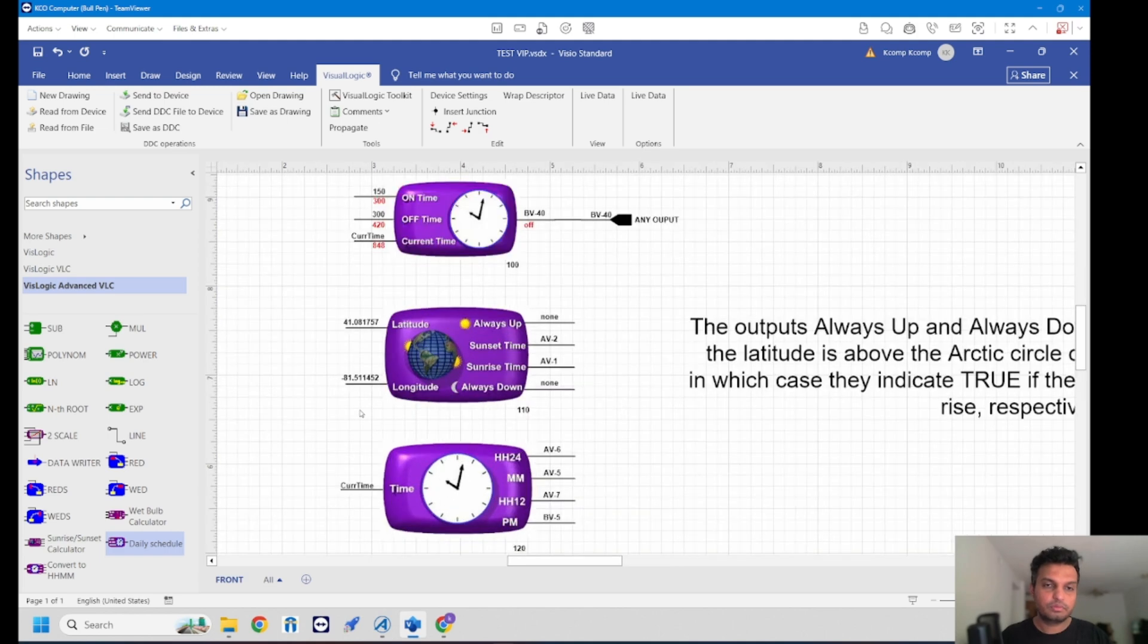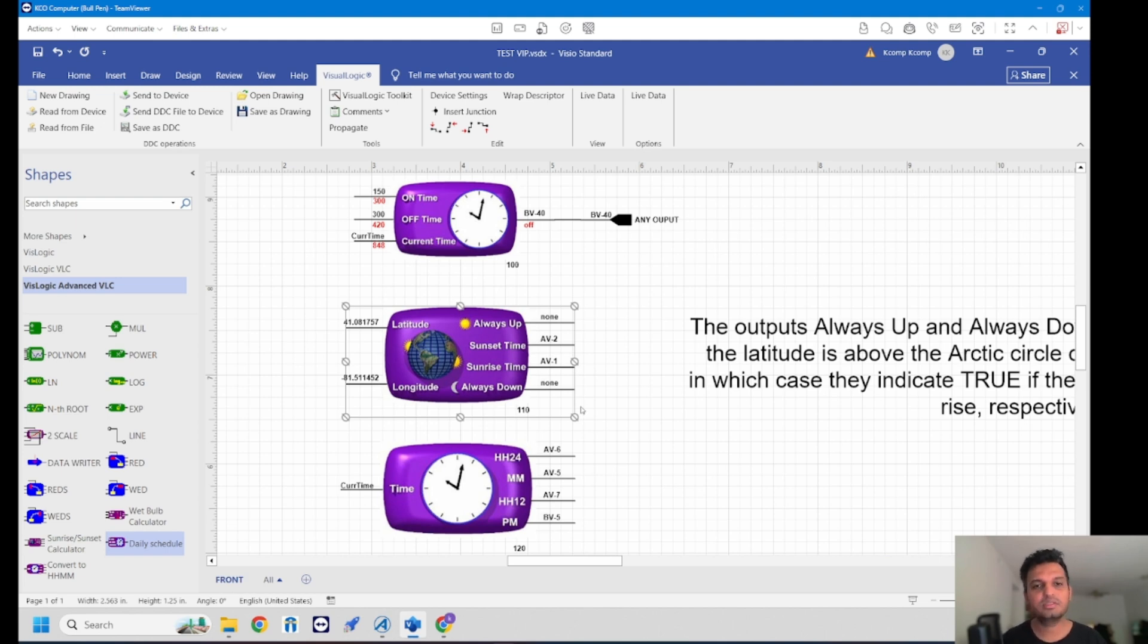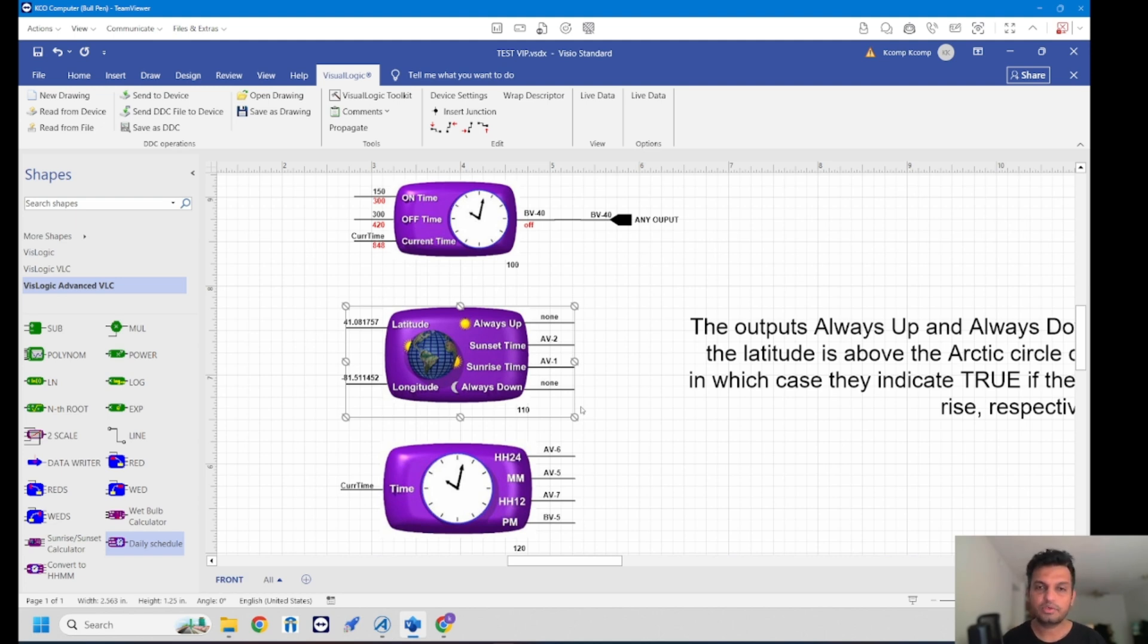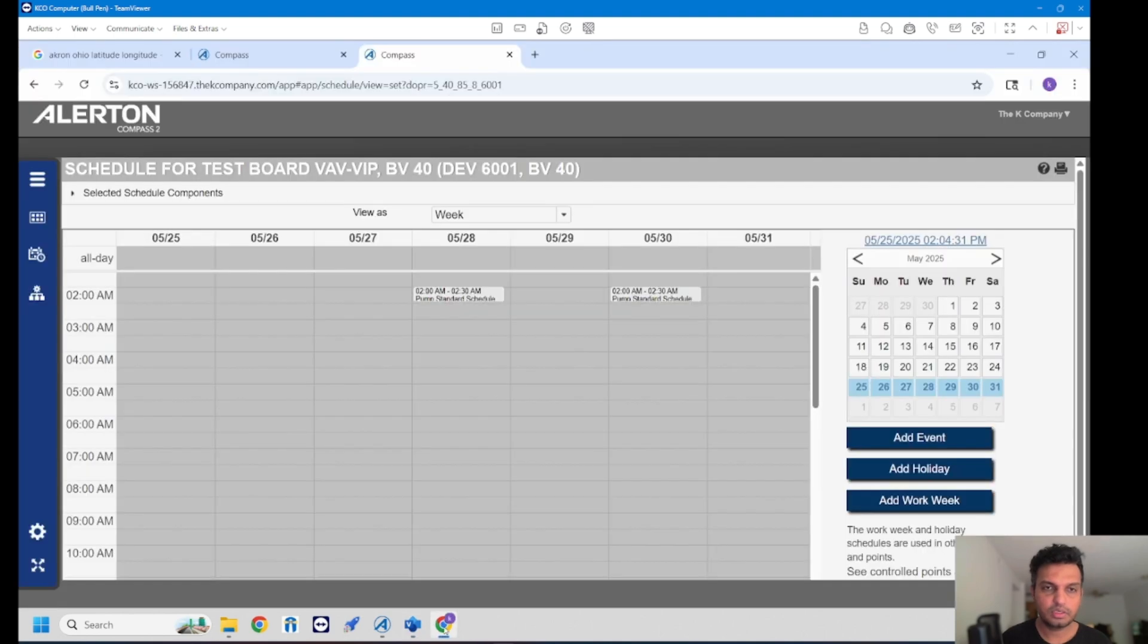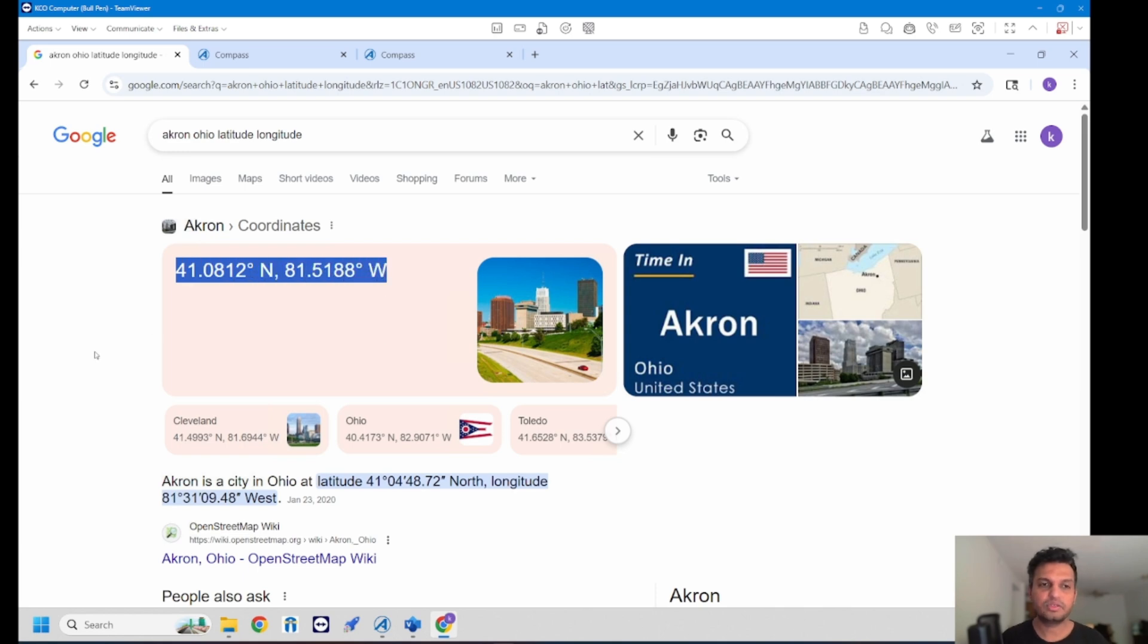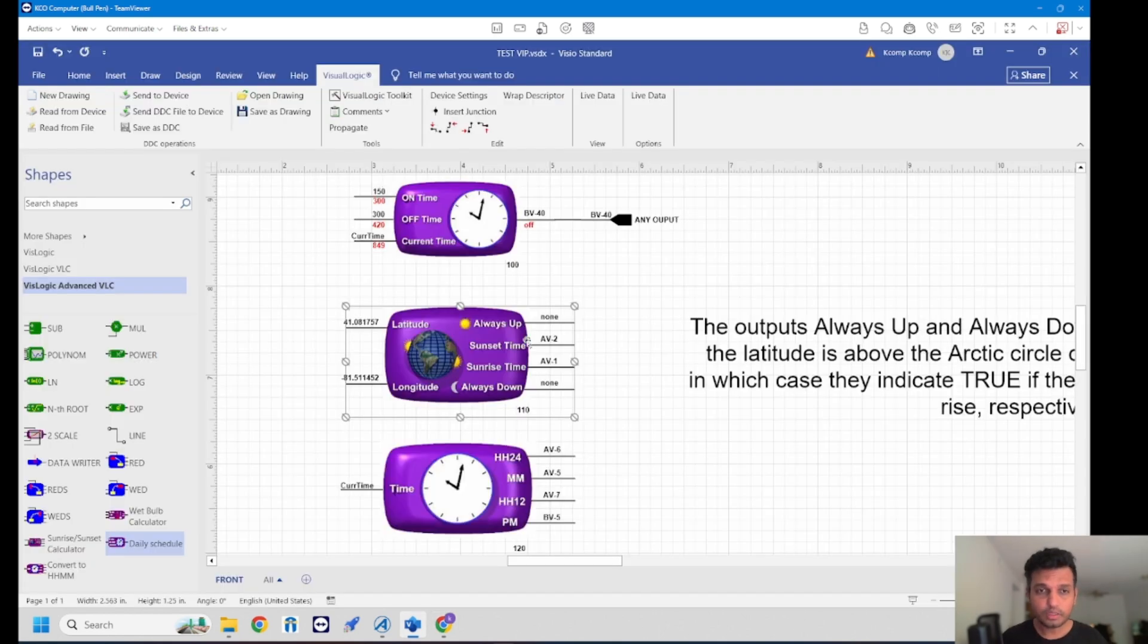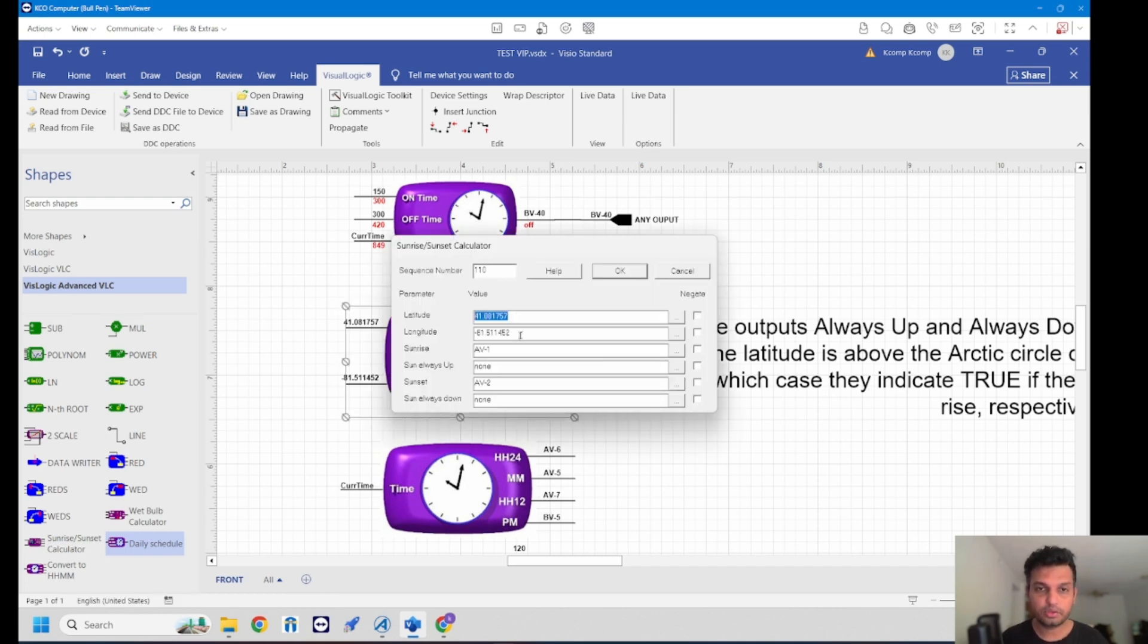We'll move on to the next one. This is a latitude and longitude function block which gives you sunrise and sunset. Now where is this used? This is used for lighting control which are outside of your building. You may have a feedback or variable that is already present from the lighting control system, but just to make sure you're having a proper turn on or turn off time you could use this function block. Whenever you're on the Google page, if you type your zone it will give you the exact latitude and longitude. You could use that and put your latitude and longitude here.